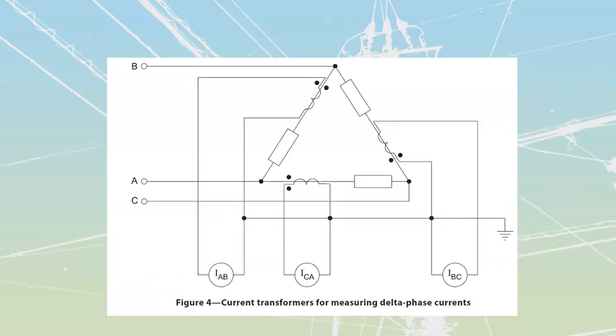Rolling back into this one - CTs for measuring delta phase currents. I can also take my CTs and use them to measure load. So here we've gone into the actual load section, these ones right over here, and I've inserted one of these into each load.